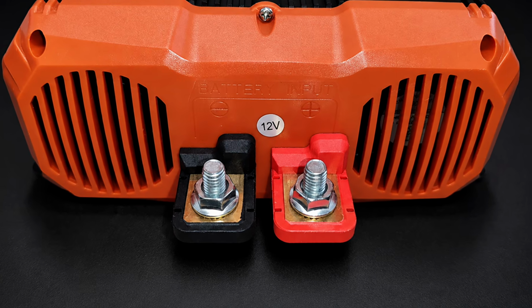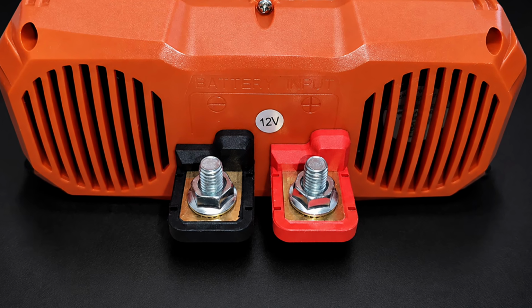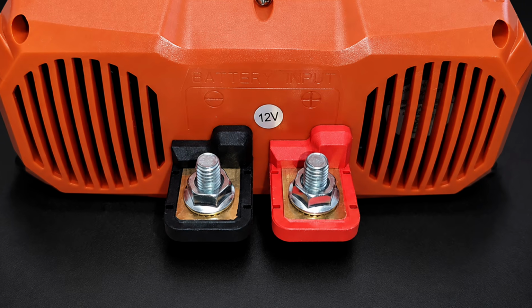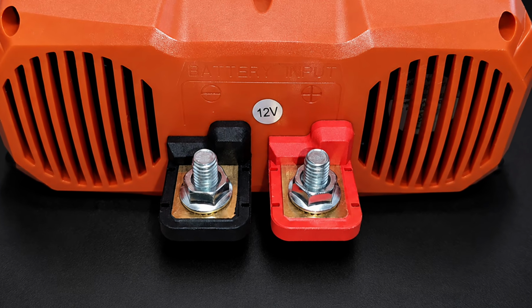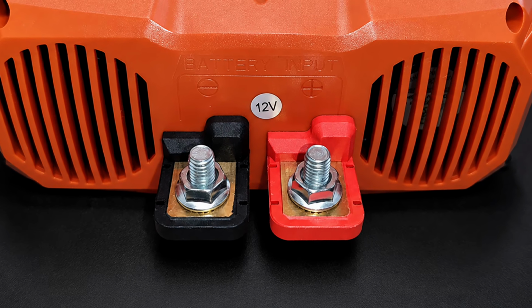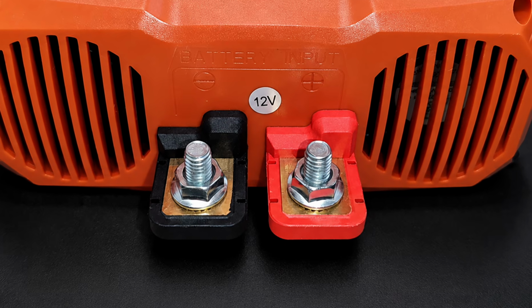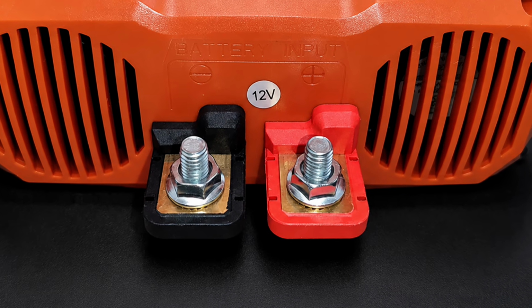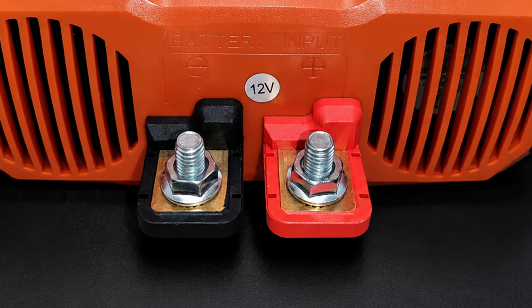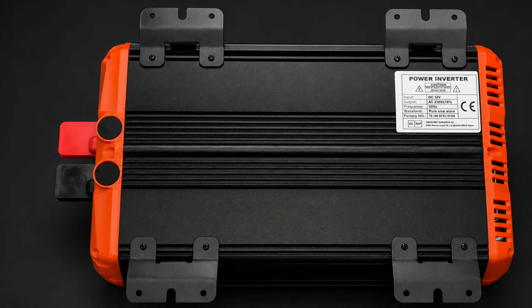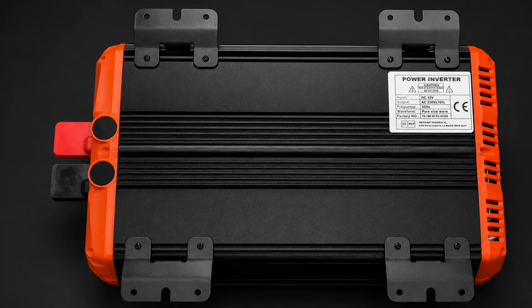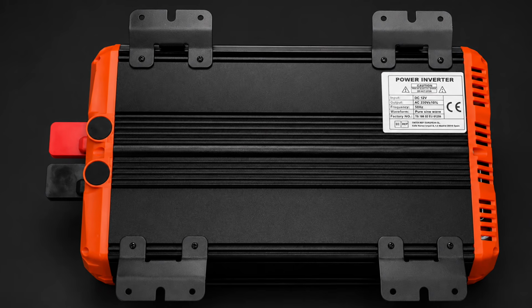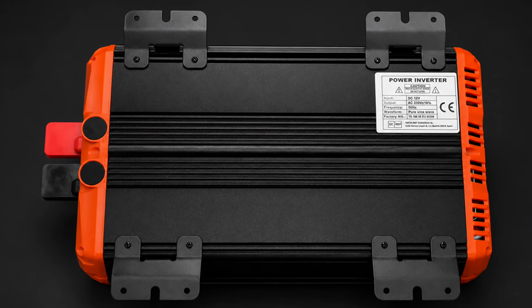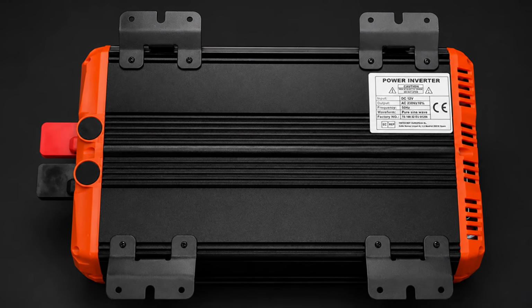For a 12-volt, 2-kilowatt inverter, this is one of the most important units, because the input currents here can be very large. Therefore, both pairs of included wires must be connected in parallel, the contact pads must fit tightly, and the nuts must be properly tightened. On the bottom side, on both edges, mounting tabs are installed, so the inverter can be properly fixed, for example on a wall, rather than simply left lying next to the battery.